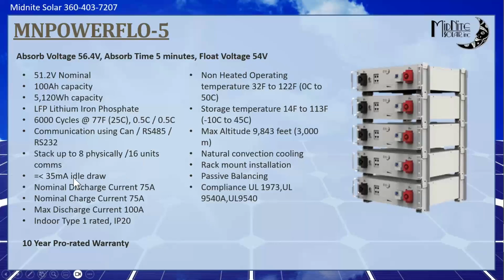The BMS, we get asked this question a lot. What is the draw of the BMS? The BMS draws 35 milliamps or less. You're right in that ballpark. Nominal discharge current of 75 amps, peak discharge current of 100 amps on this battery, and nominal charge current of 75 amps. So that's kind of your design criteria, right? Pick that 75 amps, try to stay at that or under, especially on the charging side. It's nice to charge them fast, but if you're doing a large scale system, then you might want to back that down a little bit just for longevity.